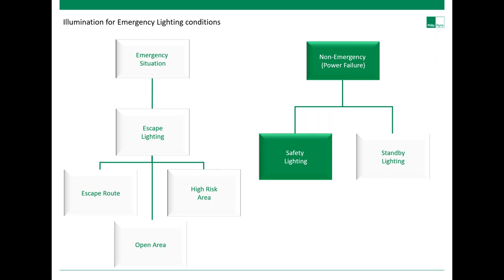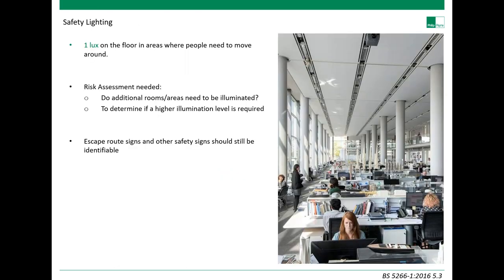Looking at a non-emergency situation where there is still a power failure: safety lighting is lighting that allows occupants to remain in the building where there isn't necessarily an immediate evacuation required — referred to as a stay-put strategy. That illumination needs to be 1 lux on the floor in areas where people need to move around. The safety lighting must be connected to a battery capable of operating for at least one hour to ensure everyone will have time to exit the premises in an emergency. Risk assessments remain essential, and escape route signs and other safety signs should still be identifiable.